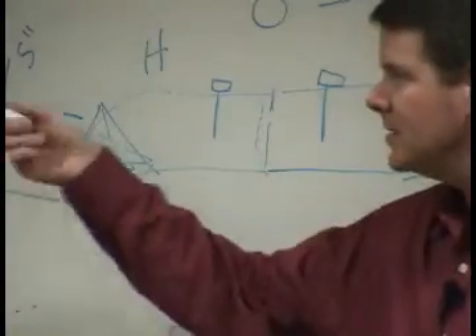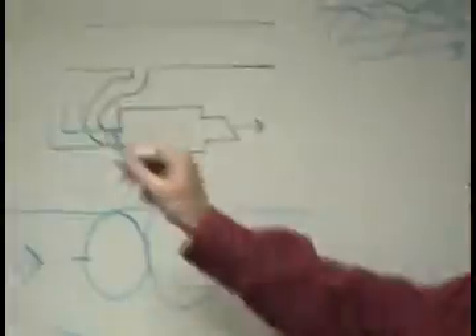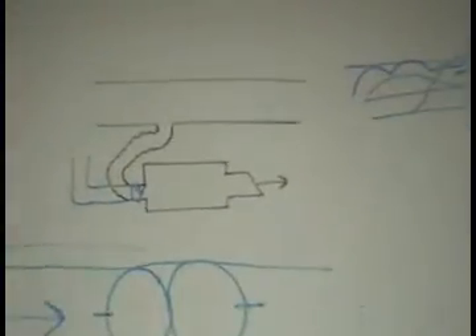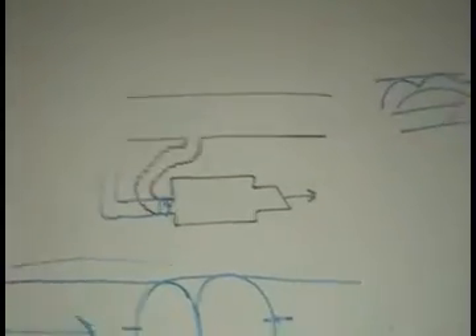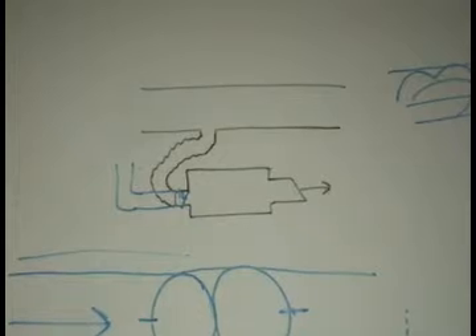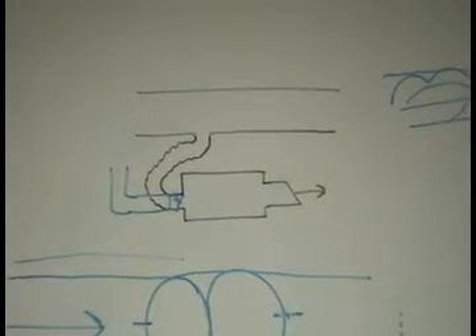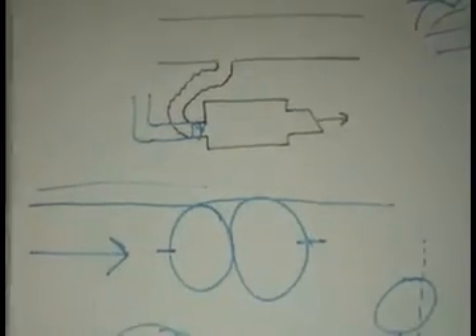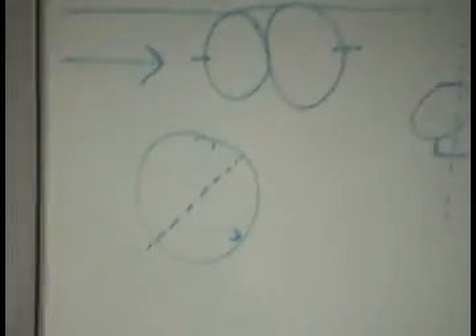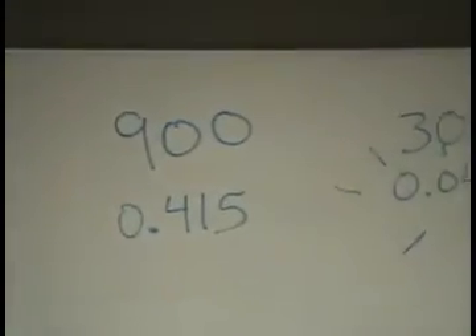There's a lot of these manufacturers that will come with the pitot coming off of them, and they'll have little plastic T's with a plug in the T, so that when the balancer comes along, he can take those plugs off and plug his meter in there and see what the differential is across it. I see those things crack or split, or the little rubber plug in the T falls off or gets old and deteriorates and falls away. I just cut them out. I would just remove those suckers. Get rid of them now. We have enough trouble with CFM. We don't need any help.